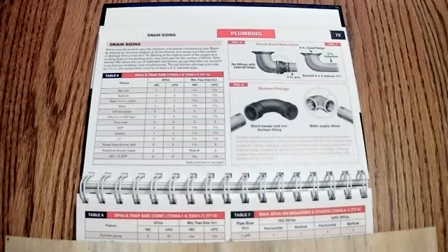Some places will use the IRC code or the IPC code, either direction, and the variances according to the code will tell you to use a 2-inch trap. For additional shower heads, it says see note B, and I don't see note B there. Oh, the table continues on the next page. A water closet is 1.8 gallon, and they're giving you 3 fixture units on that. In almost all cases, that's going to be on at least a 3-inch trap line.